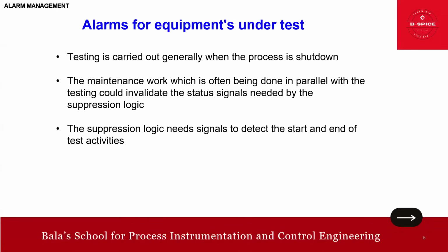An alternative approach is to provide facilities so that operators can manually demote predetermined groups of alarms to a status at which they are displayed but do not generate an audible indication or require acceptance. This approach is relatively simple to implement but does require responsible and systematic use by the operator to avoid alarms being left demoted when testing is completed.